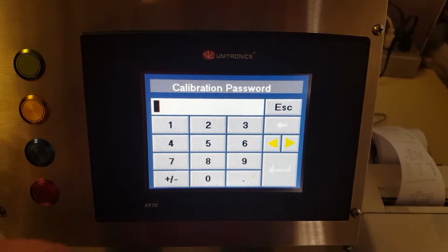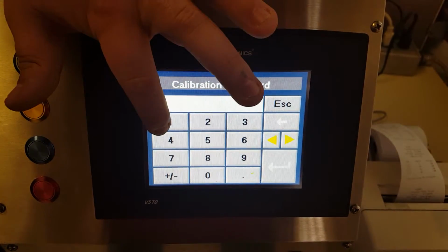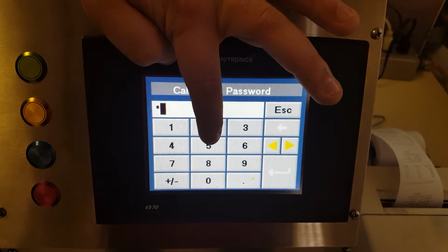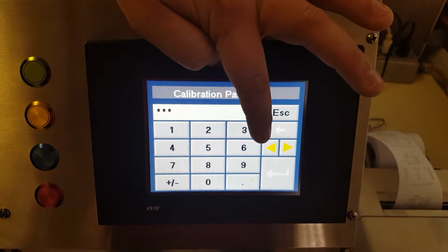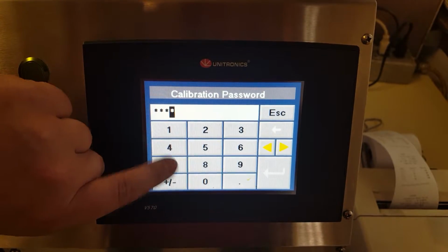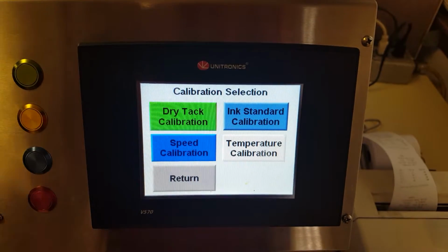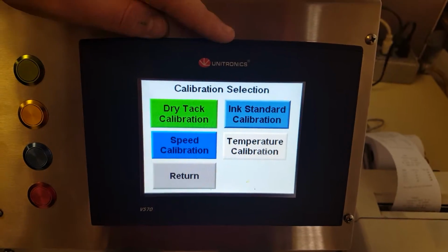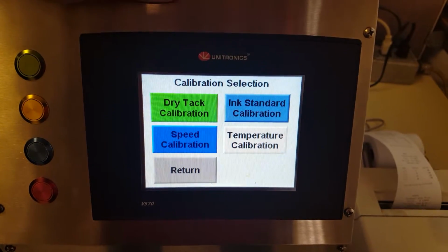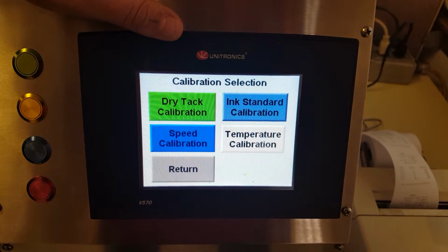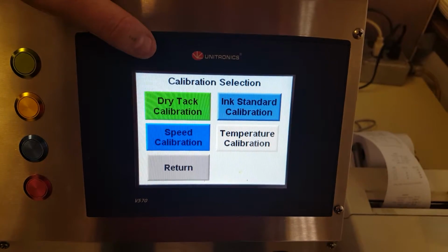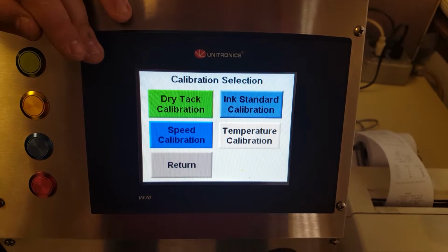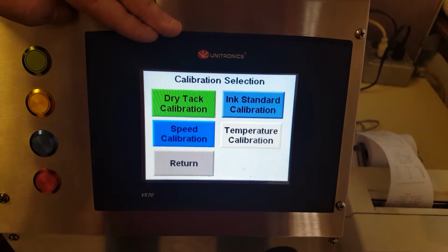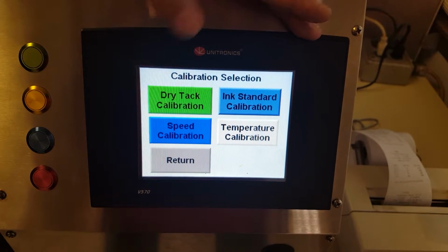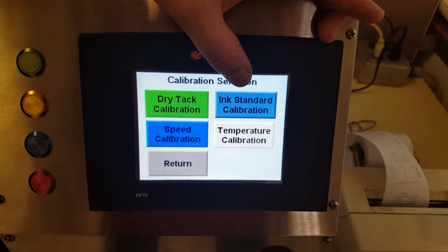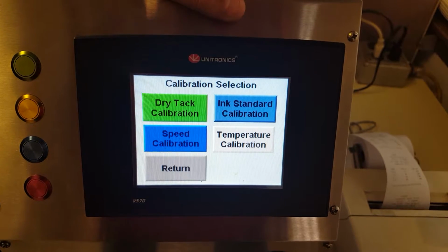We select it. It's also password protected, for the simple reason that a lot of times we don't want people from different departments or different shifts changing your calibration settings and giving you different test results. Passwords are basically the same from screen to screen and can be changed by the operator themselves, but usually don't need to. That's more of a question for later. But for now, when we get into the screen, you'll see we have several different calibration modes here: one for your dry tack, one for your ink standard, one for your speed, and one for your temperature.